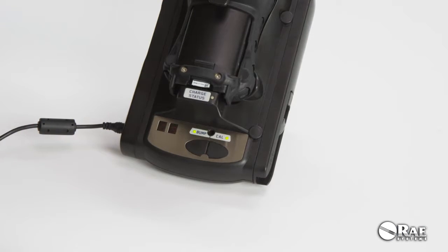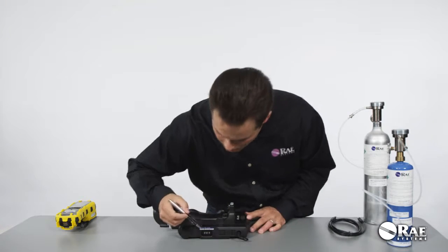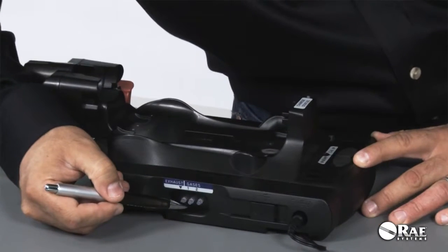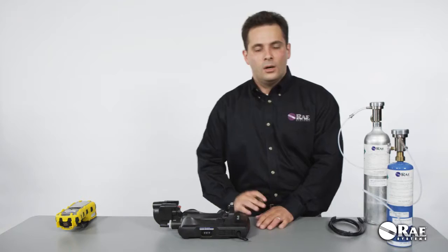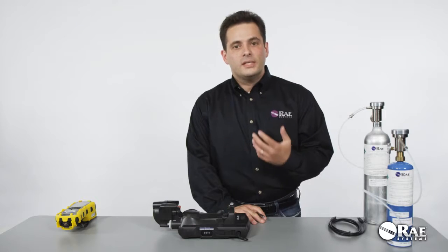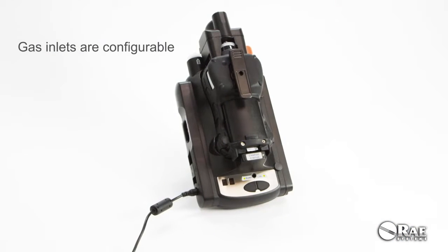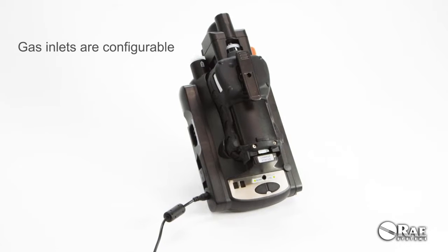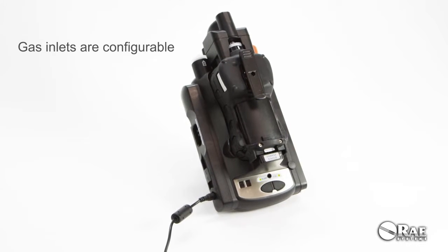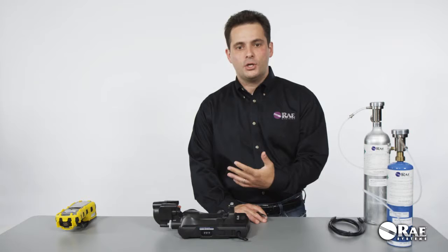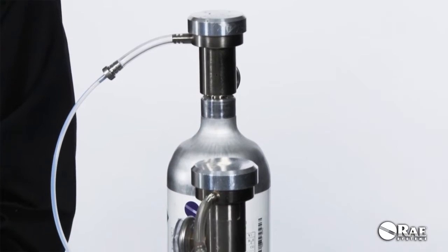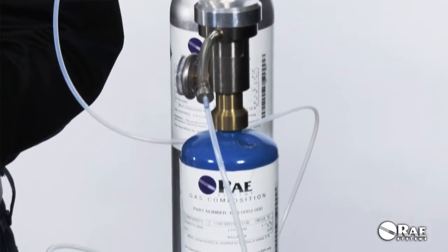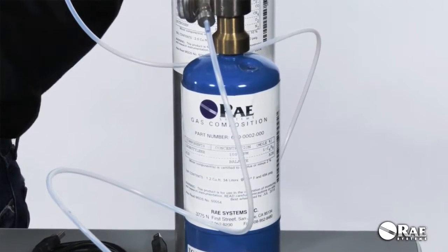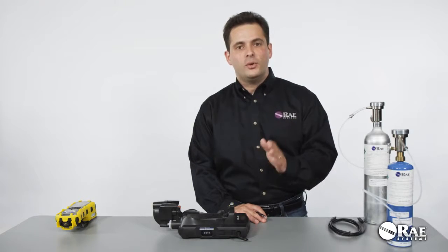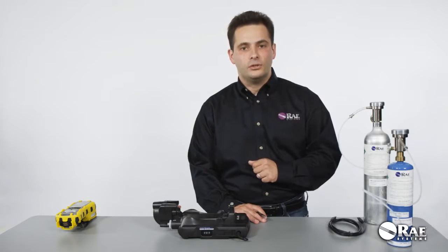Next thing to do is to connect calibration gas. Standalone cradle has 2 dedicated gas inlets, gas 1 and gas 2, and an exhaust port. The beauty of the AutoRAE 2 is that the inlets are configurable, and you can set them up to match the configuration of your MultiRAE. The default configuration for the inlets on the AutoRAE 2 Cradle is to support the basic configuration of the MultiRAE, which includes the PID, CO, H2S, O2, and LEL sensors.